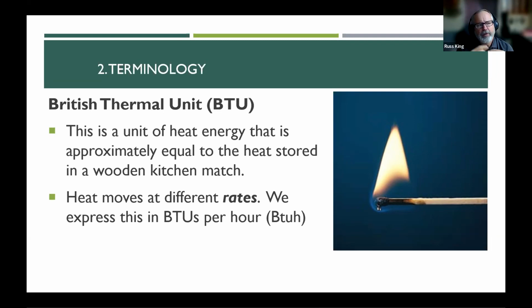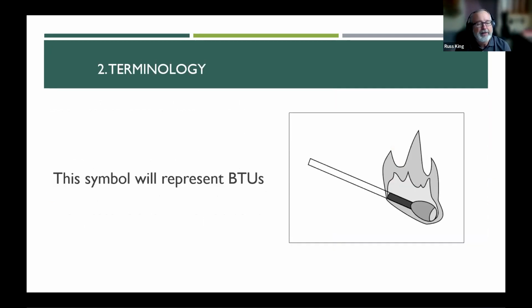So if you go look on your furnace and it says it's a 40,000 BTU furnace, what they really mean is BTUH, BTUs per hour, okay? So a 40,000 BTU furnace means that it's putting 40,000 kitchen matches' worth of heat into your house in 1 hour, okay? And air conditioners are rated in the same way, but instead of adding heat, they're removing heat. So if BTUs are hard to conceptualize, think of it as kitchen matches. I've got a 40,000 kitchen match heater, and my air conditioner is removing 20,000 kitchen matches per hour of heat from the house, okay? So that might help too. On some of these diagrams, we're going to represent BTUs with these little flying kitchen matches, okay?